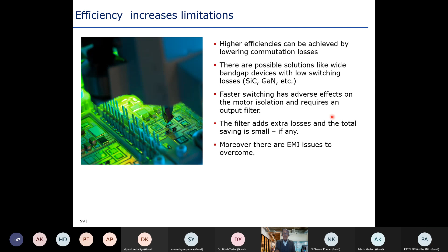Analyzing drive efficiency from a system perspective instead of a component perspective opens opportunity. Like if you look at the higher switching frequency, in some applications like a chemical plant, you cannot connect the drive directly to the motor. You need to have an LC filter in between in order to reduce the rate of rise of voltage and to support the lifetime of the connected motor. But if you increase the switching frequency, then your design of the LC filter gives promising results. You can reduce the size of the LC filter. It is compact in size.